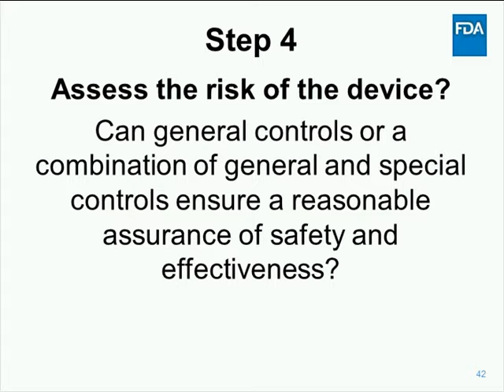Depending on how similar the devices are, the special controls used for the Serena device could provide a useful guide to many of the special controls for our hypothetical daily stim device. However, special controls cannot be fully defined until all valid scientific evidence, including any necessary clinical data, is collected. Examples of special controls might include clinical and/or bench testing, and labeling to mitigate risks of ineffective treatment, seizures, adverse tissue reactions, or electrical shocks. One of the first things you should do in making this assessment is to create a risk assessment of your device and create a risk management plan to address all the risks associated with your device.